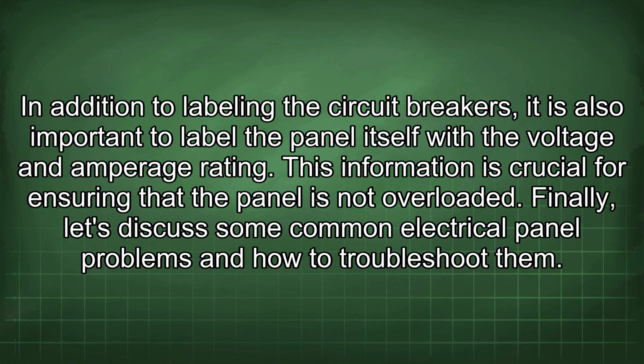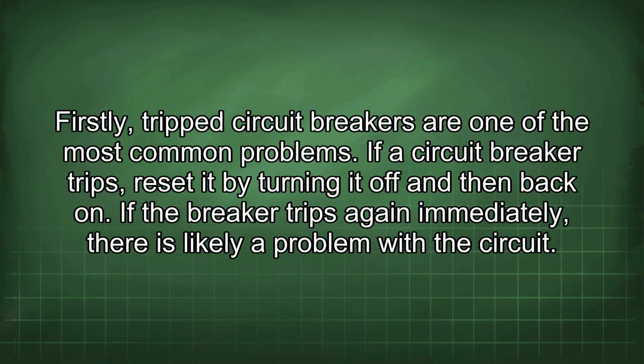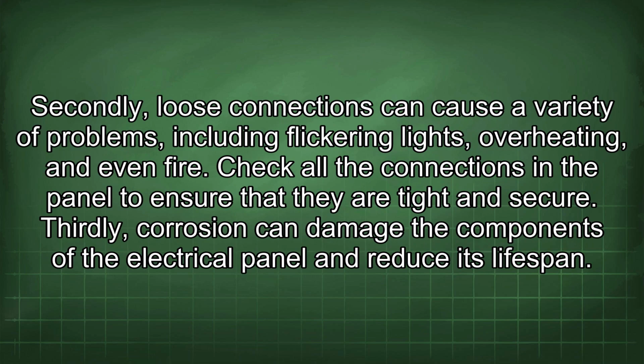Finally, let's discuss some common electrical panel problems and how to troubleshoot them. Firstly, tripped circuit breakers are one of the most common problems. If a circuit breaker trips, reset it by turning it off and then back on. If the breaker trips again immediately, there is likely a problem with the circuit. Secondly, loose connections can cause a variety of problems, including flickering lights, overheating, and even fire. Check all the connections in the panel to ensure that they are tight and secure.